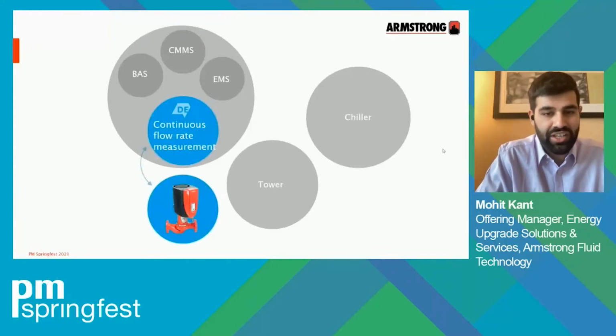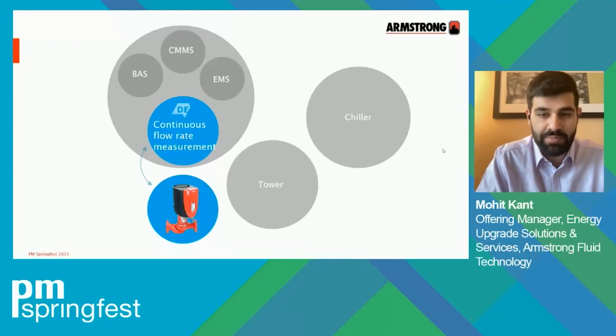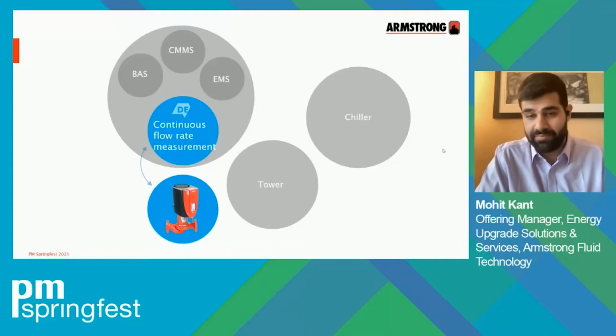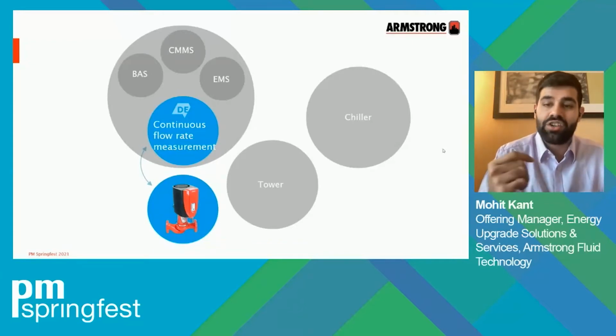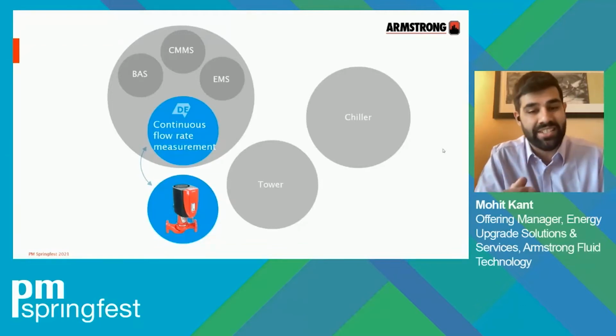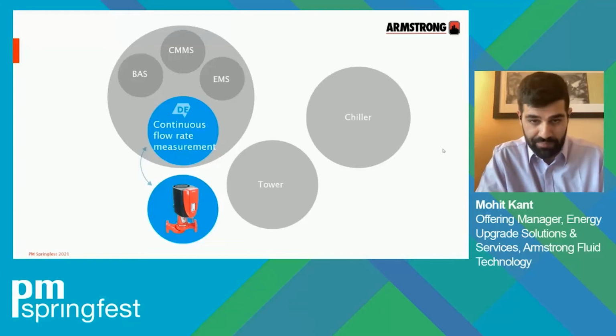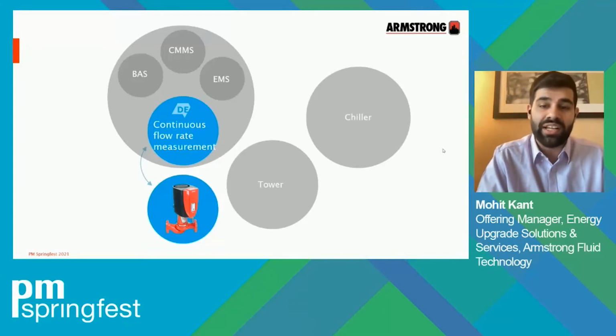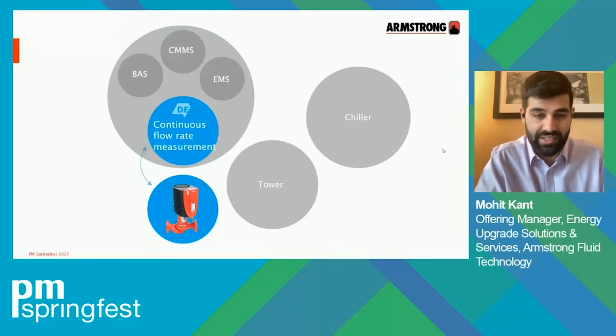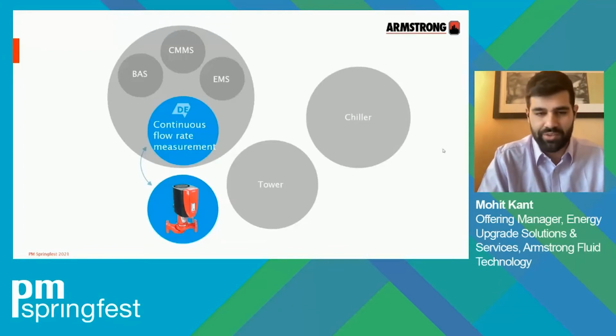New integrated sensorless pumping technology can measure flow rate just by knowing its horsepower and speed. The pumps provide an enormous amount of information directly back to building operators and building systems relating to system performance. This data is available directly from the pumps through serial communications to the BAS, through Wi-Fi connections to a smartphone, tablet, or PC, and of course on the pump display screen.